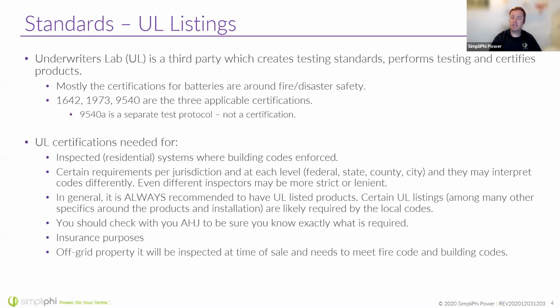We also obtained a 9540A test protocol. This isn't a certification -- what happened is UL, or third-party testing, took one of our energy storage systems and put it inside a test chamber. Then inside one of the battery modules, they wrapped one of the battery cells in a heating wrap and forced that cell into thermal runaway. It took a lot of energy to do that. Once it did go into thermal runaway, they watched what happened and issued test results.